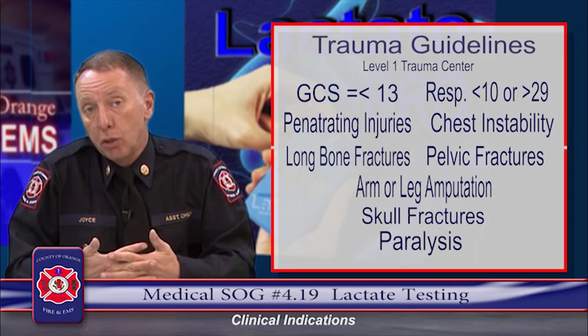And then we'll go through the actual operation of the Lactate Pro machine itself. It's worth saying that this machine is FDA approved for its purpose, and there is a CLIA waiver to perform this actual test. So several of the things you have to do. If you've decided that you're going to use this test, like all tests, one test all in and of itself is of very little use to you. You have to do serial testings.